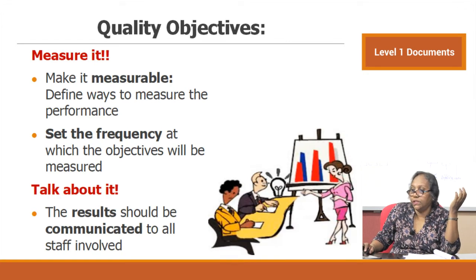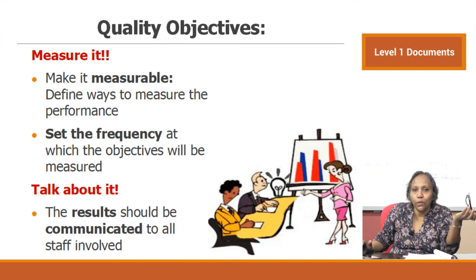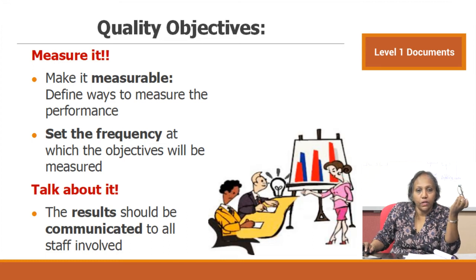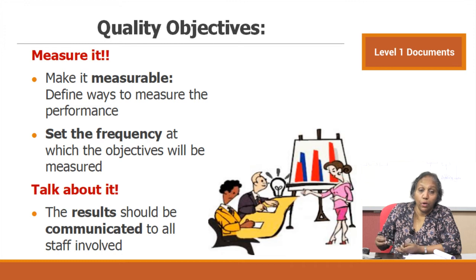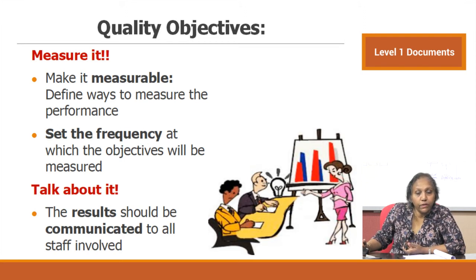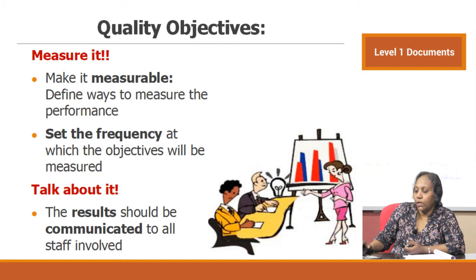Make objectives measurable — define ways to measure performance and set the frequency at which objectives will be measured. Most labs set quality objectives on an annual basis, but you need to measure progress more frequently, perhaps quarterly. This measurement should be done by management. Management and technical staff should sit together and understand whether there is progress toward objectives or whether progress has stalled. Results should be communicated to all staff involved.